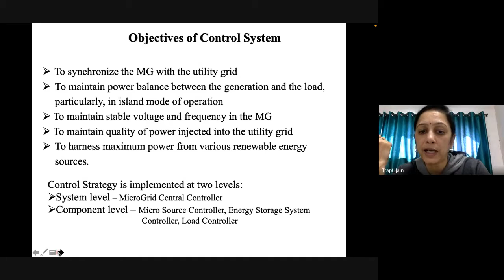So we'll first see the microgrid central controller, which is at system level. Its tasks are to provide power set points for the DG units, as we've seen earlier, then economic scheduling, to control peak load, to control non-critical loads during islanding, to minimize system losses, to detect islanding conditions based on measurements at the PCC, to initiate resynchronization with the local controllers when the grid is restored, to monitor power flows through local generating units and the PCC, and to make the islanding decision.